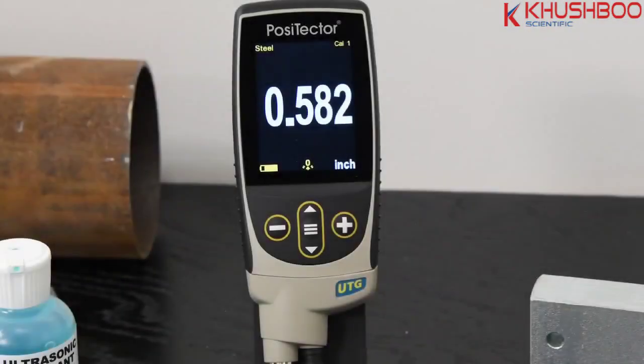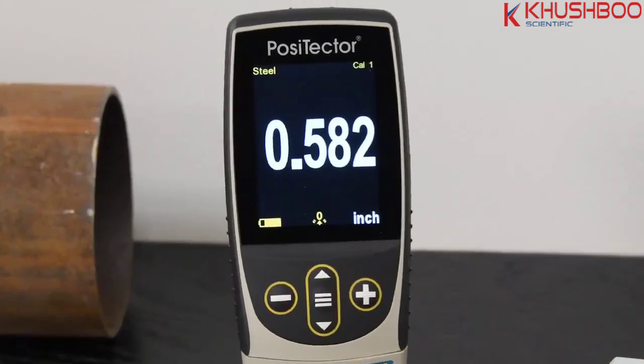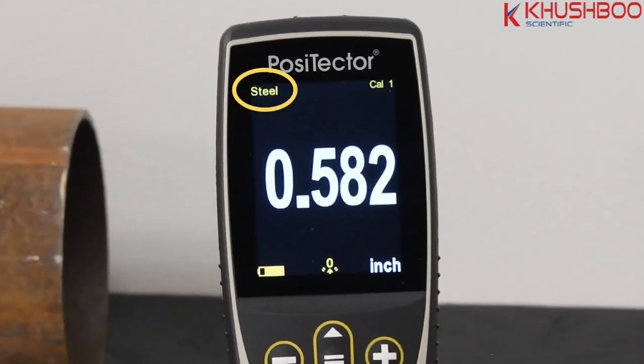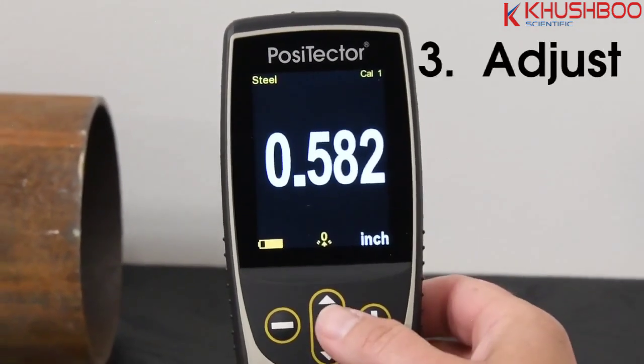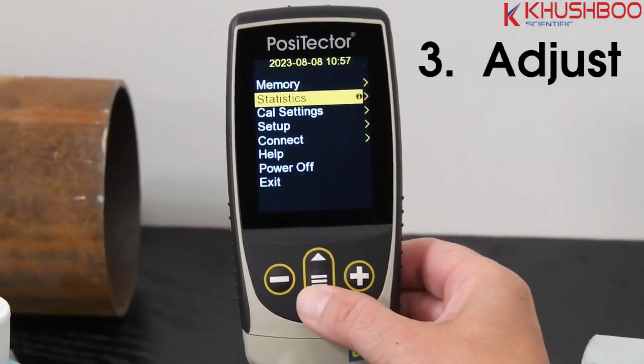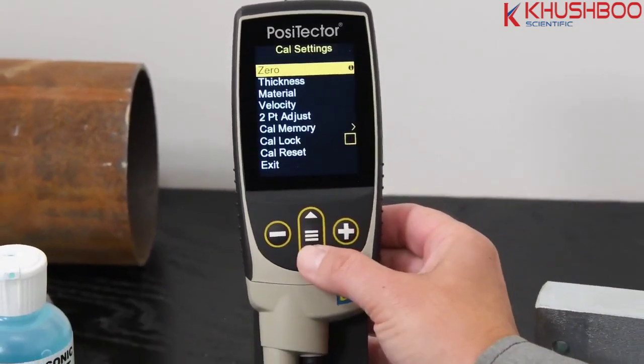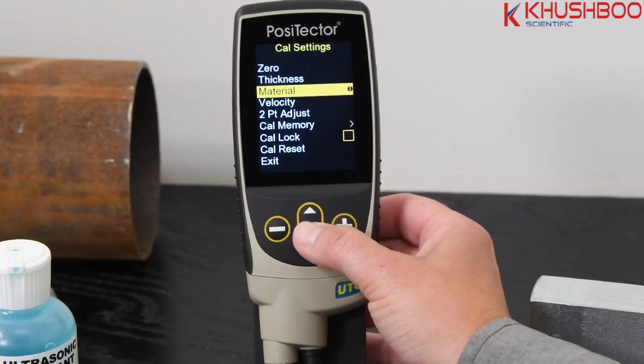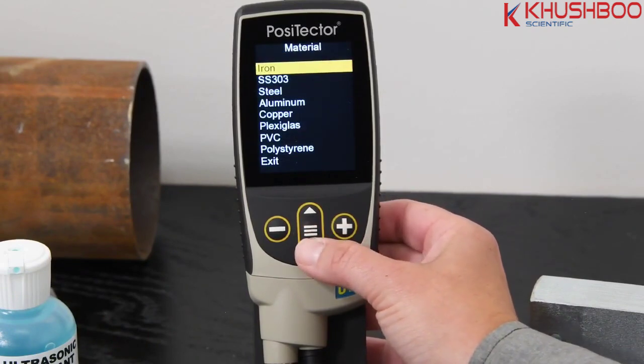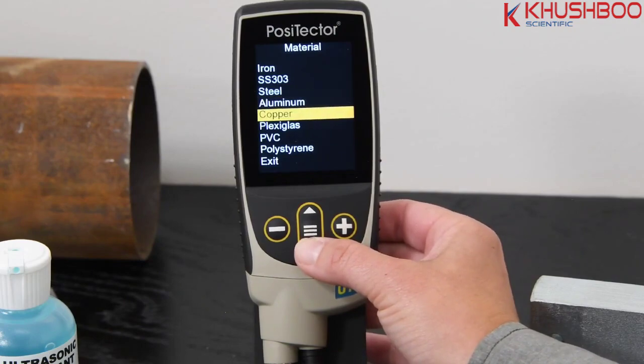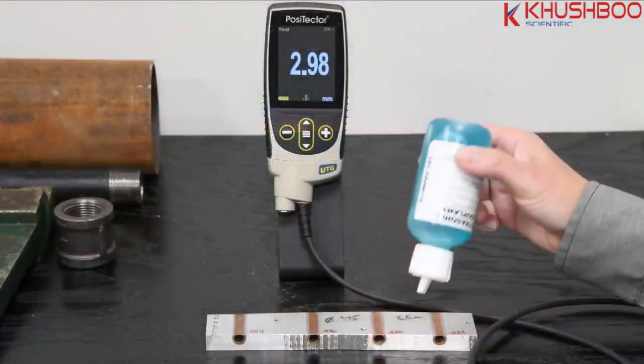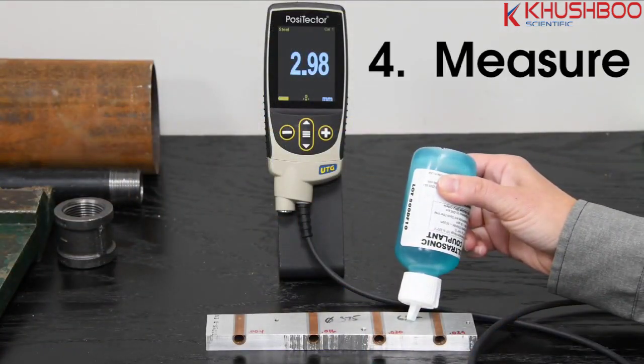The PosiTector UTG is pre-configured to measure carbon or mild steel. For other materials, an adjustment is required to account for different acoustic velocities. The PosiTector UTG makes this process easy. Simply select Material from the Cal Settings menu and select from a list of common materials. The PosiTector UTG is now ready to measure.